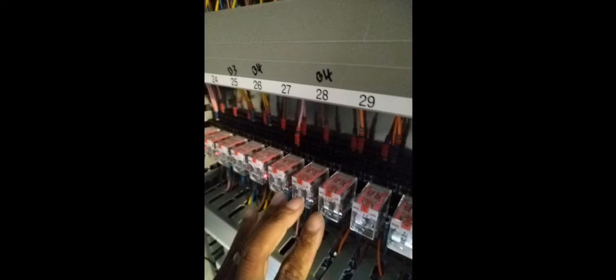In the BMS panel, I was trying to see which relays were lighting up when I turned on the selector switch, when the call for heat for the boiler came on. So when the switch live sent 8 volts DC over to the PCB, I think one of the relays was like the lamp indicator coming on.